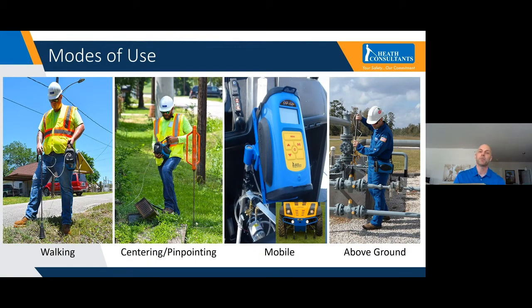And by doing that, we need to take below ground or subsurface readings. And you can see the next picture there talks about centering and pinpointing. So what I mean by that is to find out the spread of that leak or the severity of that leak, we want to be able to check for readings under the ground. And to do that, you need a device that's capable of detecting percent gas in air, which again, the DPIR does. So on the centering side, what I mean by that is you want to try to find the spread of the leak, like how far that leak is spreading. So when we're talking about the surface sample readings, that's just telling you where that gas happens to be venting at. So, depending on your surface cover or the time of the year, whether there might be frost in the ground, where the gas vents could be completely different from the spread of the leak.